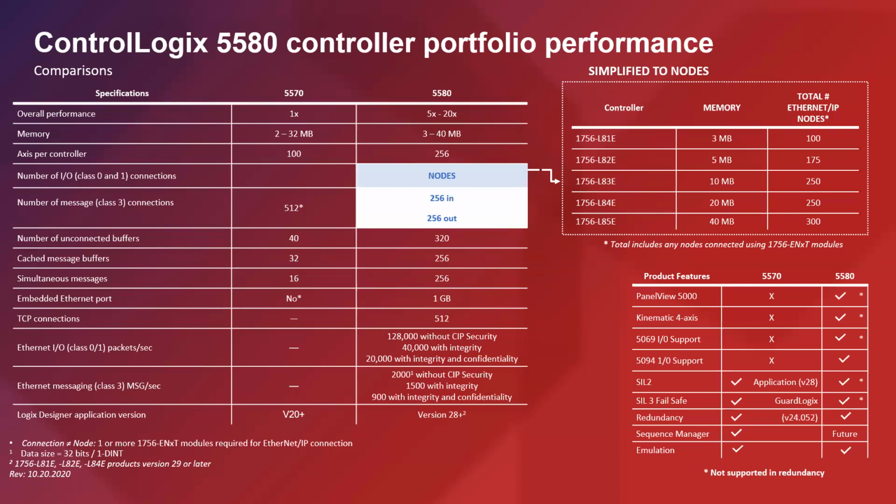And it does support up to version 33. So the L7 family for Studio 5000 is going to work from version 20 all the way up to version 33, which is the latest version of Studio. Whereas the L8 family kind of came in, I think, around version 28. And so it's going to be 28 through version 33. So if you're trying to support some older versions of installs of Studio 5000 for any reason, and you can't move up to a newer version, perhaps the L7 is still what you want to look at there as well. All right.